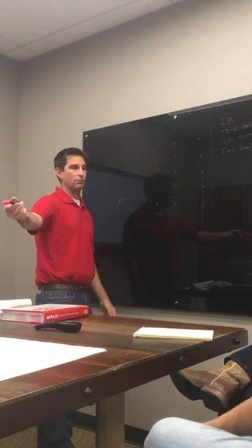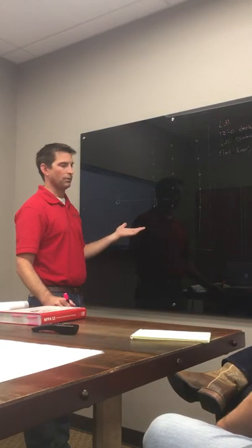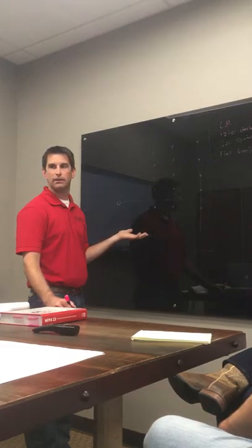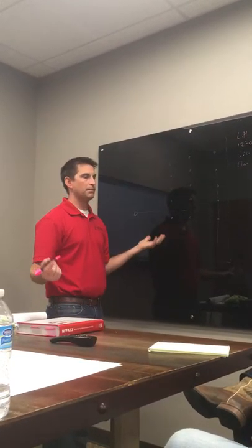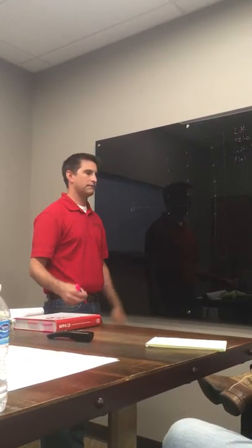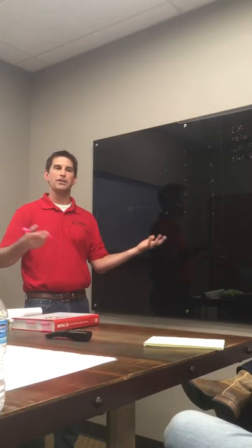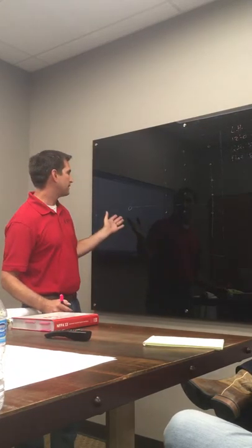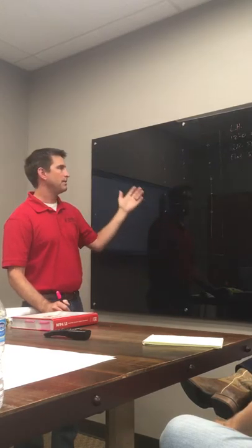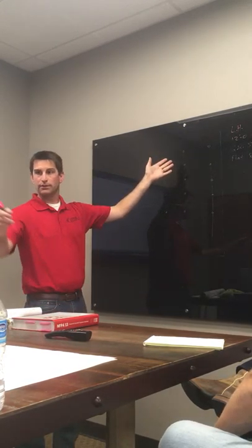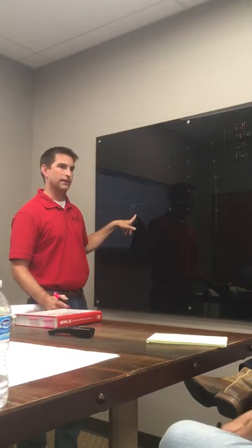He said it's the most remote location, typically. You said it's the most hydraulically demanding, so could we have more than one remote area, more than one design area? If they're equally hydraulically demanding, right? Yeah, if everything's typical, we may only have one, but we could essentially have 400 design areas in our building to prove different situations or different hazards. But in this case, if it's all the same occupancy, it's all light hazard, the space is the same and all the pipes are the same, then I can pretty much go to the furthest location and prove it works there, and if it works there, then it'll work here because it's closer to the riser, right?